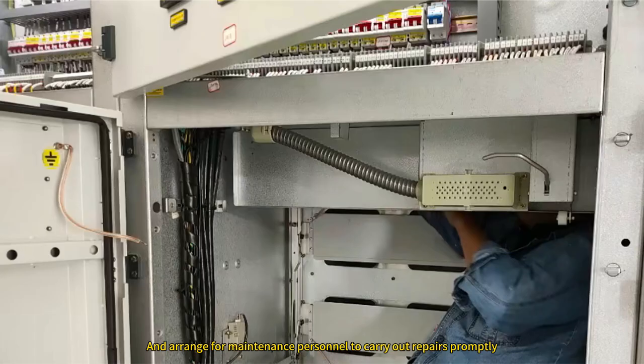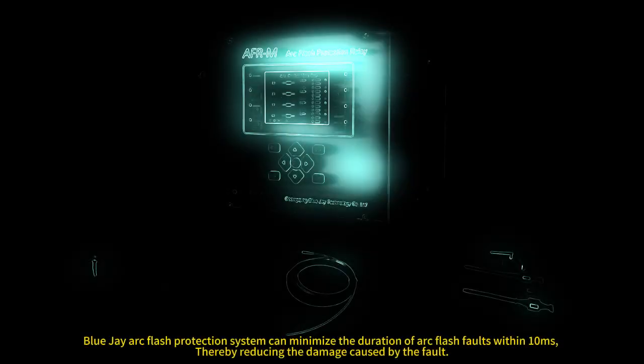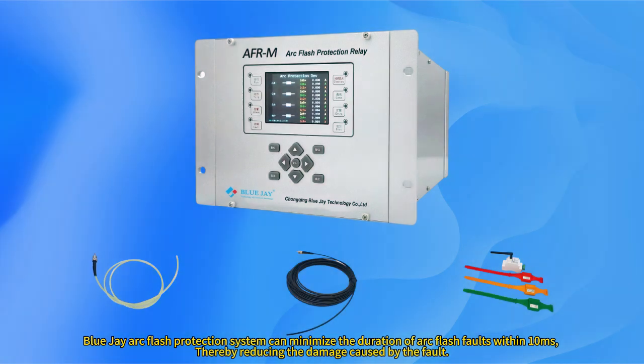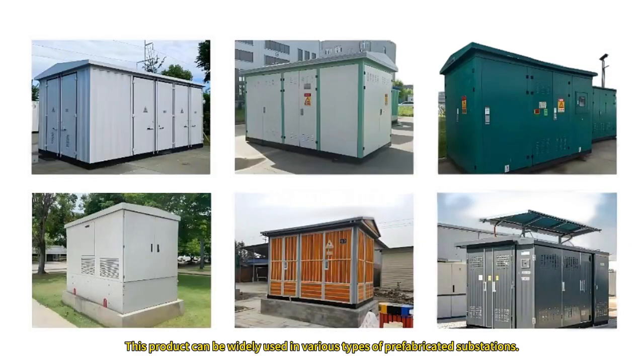carry out repairs promptly. Blue Jay Arc Flash Protection System can minimize the duration of arc flash faults to within 10 ms, thereby reducing the damage caused by the fault. This product can be widely used in various types of prefabricated substations.